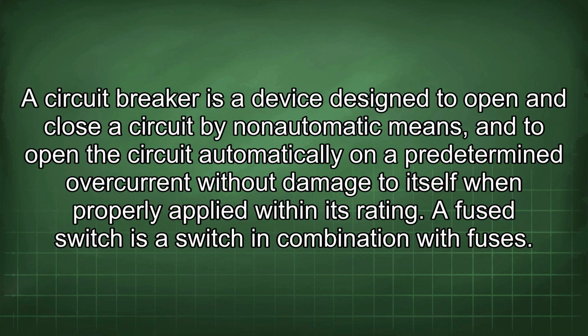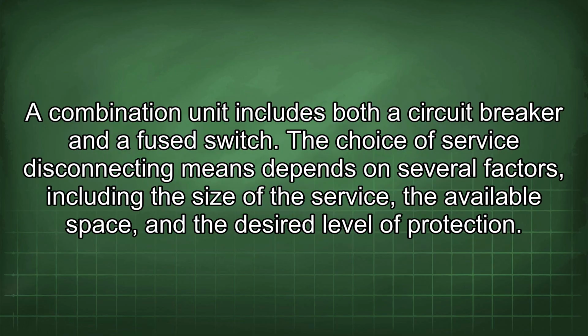A circuit breaker is a device designed to open and close a circuit by non-automatic means and to open the circuit automatically on a predetermined overcurrent without damage to itself when properly applied within its rating. A fused switch is a switch in combination with fuses. A combination unit includes both a circuit breaker and a fuse switch. The choice of service disconnecting means depends on several factors, including the size of the service, the available space, and the desired level of protection.